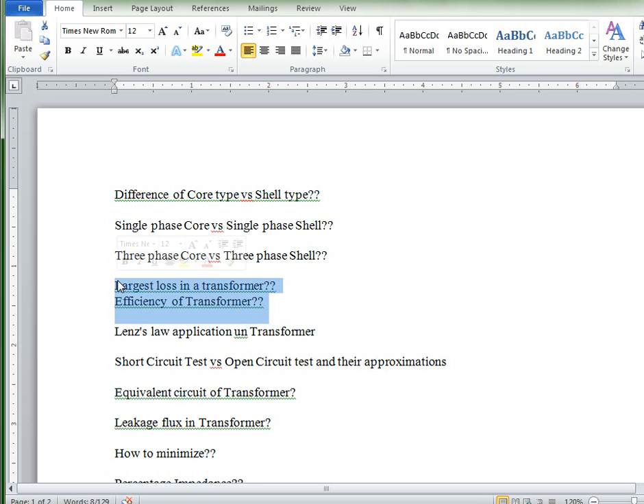What is the efficiency of a transformer? Can someone tell me a range? A design below 90% gets rejected by WAPDA. 95% plus at full load and 70% load efficiency is required by every manufacturer, or at least the WAPDA or LESCO people. They have a design criterion that the transformer should have maximum efficiency near almost 70 or 80% of the load. They will never ask for it at 100% of load.